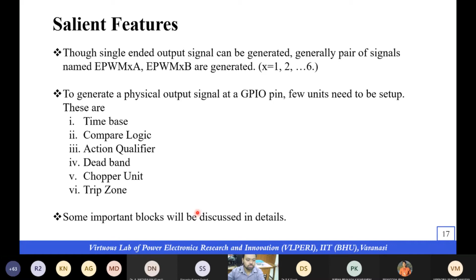Now, to generate a physical output signal at any GPIO pin, that is a general purpose input output pin present on the docking station, a few units need to be set up. These units are the time base unit, compare logic unit, action qualifier unit, deadband unit, chopper unit, and trip zone unit. These units are already shown in this architecture block diagram. So we need to set up all the units, right?